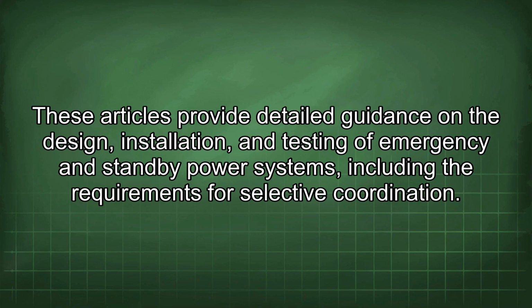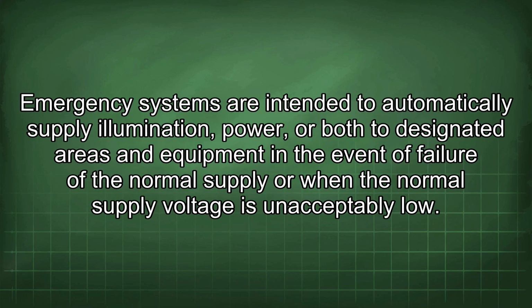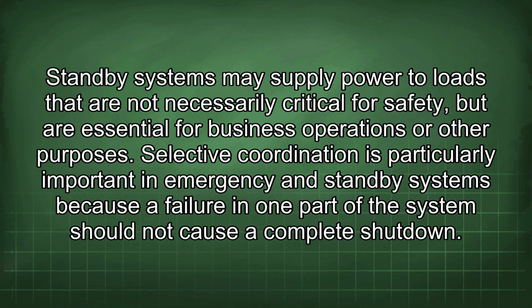These articles provide detailed guidance on the design, installation, and testing of emergency and standby power systems, including the requirements for selective coordination. Emergency systems are intended to automatically supply illumination, power, or both, to designated areas and equipment in the event of failure of the normal supply or when the normal supply voltage is unacceptably low. Standby systems may supply power to loads that are not necessarily critical for safety, but are essential for business operations or other purposes.